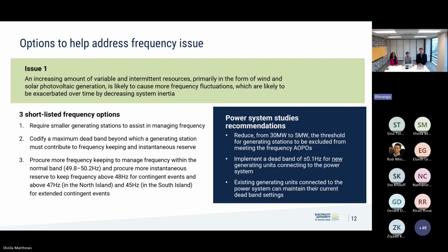Looking first at the option around getting smaller generating stations to contribute more to supporting frequency: the 30 megawatt threshold currently in the code was set a long time ago, over 20 years back. At the time it was introduced, the thinking was that it would be subject to review over time, but that review never happened. Now, with the introduction of inverter-based resources and the uptake of wind and solar coming down the pipeline, it's an appropriate time to look at that threshold. The system operator did a study for us on an appropriate reduction, and their recommendation is to go with 5 megawatts.